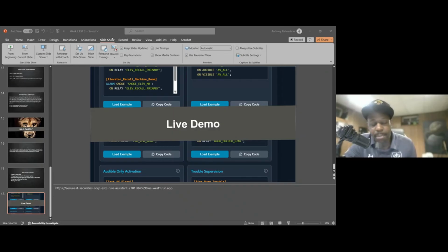Partitions work the same as a burglar alarm system. So you can separate your zones by, you will never use this right here. But this tab here, service groups, this is a big tab that a lot of people will always use. Let's say a high-rise building, or a school, you could put different wings in a service group, so that way you could disable the east wing, but the west wing can still stay active.